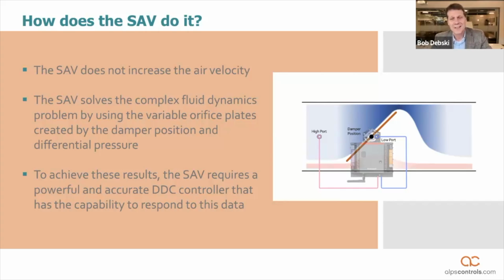The one thing you might notice is that if you look at the static pressure port, it's been moved to behind the damper. And that's going to prove to be one of the most critical changes in the design that you're accustomed to. What's important is that one simple change solves a problem that's plagued air terminals for a long time, and that's the fluid dynamics problem. That's exactly what the smart air valve does. It uses the damper position, which creates variable orifice plates, and gives us an opportunity to understand the fluid dynamics and solve the math behind what's taking place.